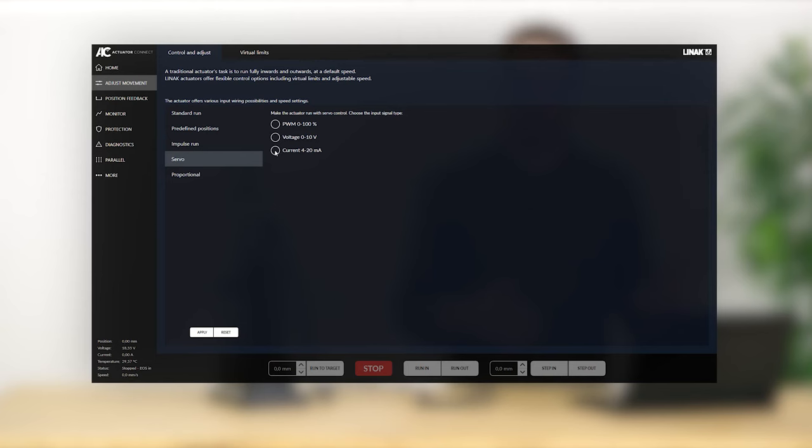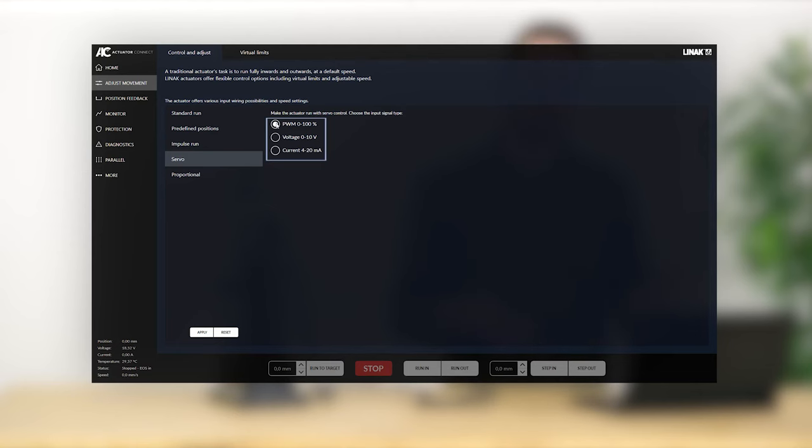With servo drive, you can use an analog input signal to control the position of the actuator. This way, the physical stroke length of the actuator is scaled according to the input signal, thereby offering full control of the actuator positioning with a signal of your own choice. As mentioned previously, these analog input signals can be 4 to 20 milliamps, 0 to 10 volts, or 0 to 100 percent PWM.